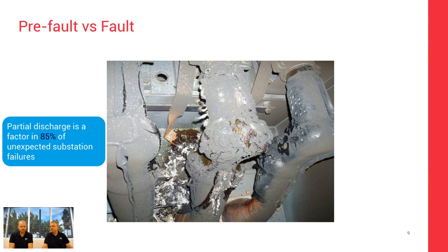Just a few comments here. Okay. How much cheaper is it to fix before failure? And then Andrew's commented, repair before failure cost is typically orders of magnitude less than failure. So the sort of failure, we would typically look at that even for a cable. If you can take a cable out of service before it fails, we work that as being usually about a third of the cost of letting a cable fail, and that's usually the smallest ratio.